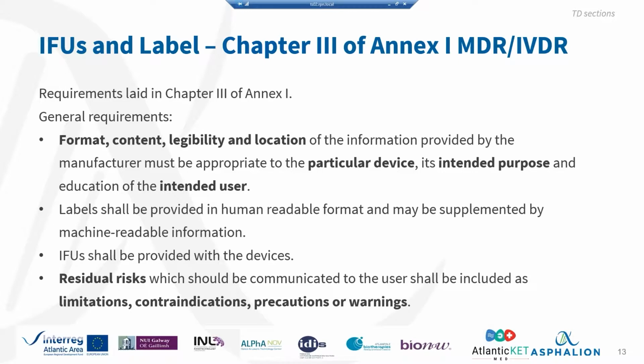Okay, it's not the same to write instructions for use for a device that is going to be used by a patient, who may or may not have training on how to use this device, than writing them down for a doctor for a specific treatment. Okay, you always have to keep in mind the background of the final intended user. So it's not the same writing for a patient than writing for a doctor. And this is something that should always be kept in mind. The text cannot be super confusing or hard to understand for people without specific scientific background.